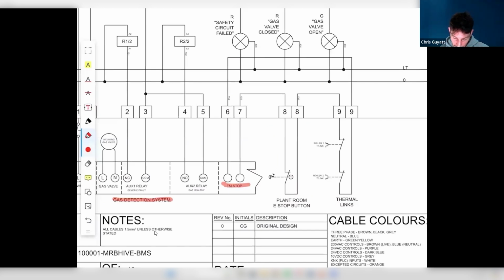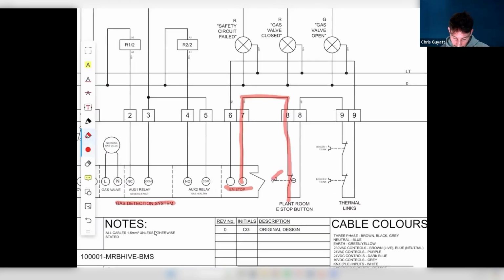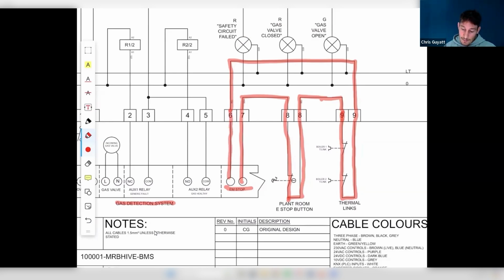Because you can see it is just a series circuit, and the e-stop here is normally closed, and then we're going back into the panel and then out of the panel, and now we're going to our boiler thermal links, and you can see that they're normally closed, so just keeping that circuit in series. This is out in the field, back into the panel, and then we're going back here. This is obviously a bit of cable, and then we're going back to our gas detection system and completing the circuit. So that's what we're looking for.